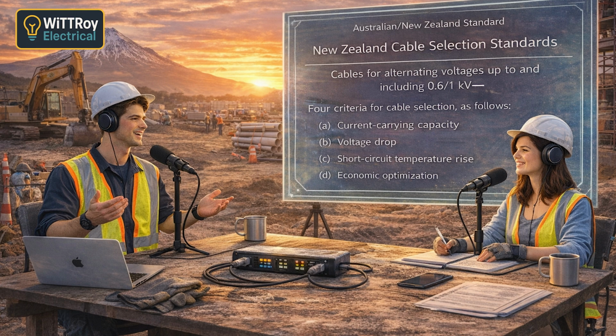Okay, this part always confuses me. Let's slow it down. Derating just means reducing the cable's current capacity because conditions are worse. Can you give me a simple example? Sure, imagine one cable in open air. Easy cooling. Now imagine 5 cables bundled together. Oh, they heat each other. Exactly. So each cable carries less current safely. So grouping reduces current capacity.